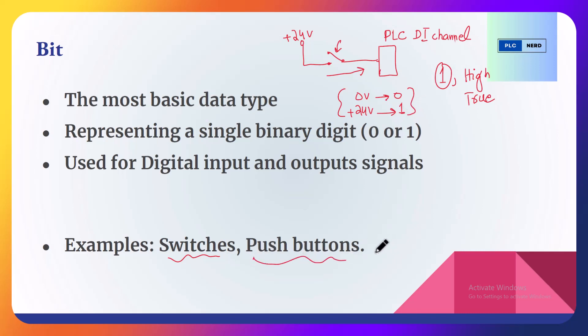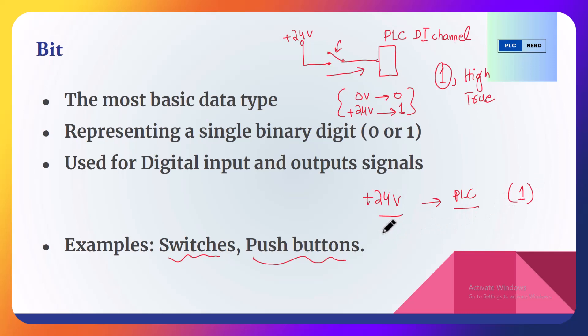We also have push buttons and other digital sensors, for example a proximity sensor. If it is sensing any metal, it will send plus 24 volts to the PLC, and the PLC will treat this 24 volts as one in programming. If no voltage is sent to the PLC, it will treat this signal as zero. So zero and one — this is the boolean, a single binary digit, and it is the simplest data type used in PLC programming.